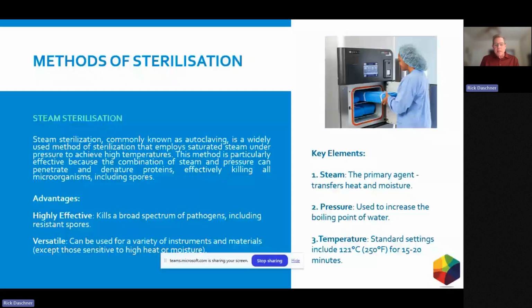Advantages: it kills a broad spectrum of pathogens, including resistant spores. It's versatile, can be used for a variety of instruments and materials, except those sensitive to high heat and moisture. And we'll talk about what you do with those products going forward here. So the key elements of this: the primary agent is heat and moisture. Pressure is used to increase the boiling point of water. And temperature standards include 121 C, but sometimes up to 132, 135, 137 C, depending on the product. And our products will be validated to a couple different temperatures that will accommodate what you need.